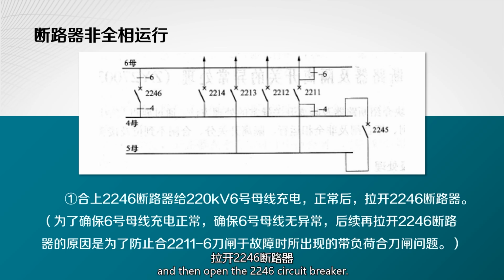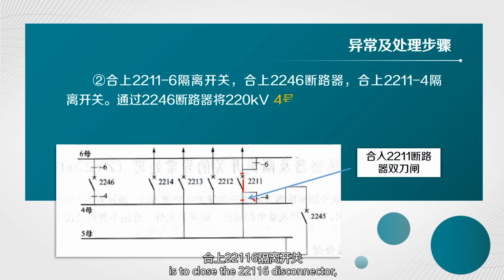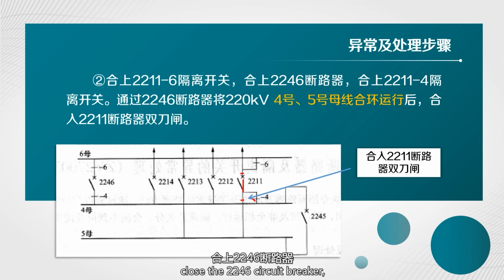After that, open the 2246 circuit breaker again. Here, the main purpose is to ensure that the number 6 bus is charged normally, and there are no abnormalities in the number 6 bus. The reason for opening the 2246 circuit breaker again afterwards is to prevent the problem of load closing. When the 2245 circuit breaker fails to close, the second step is to close the 2211-6 disconnector, close the 2246 circuit breaker, close the 2211-4 disconnector, and use the 2246 circuit breaker to close the 220 kV number 4 and number 5 bus. After operation, close the double switches of the 2211 circuit breaker.